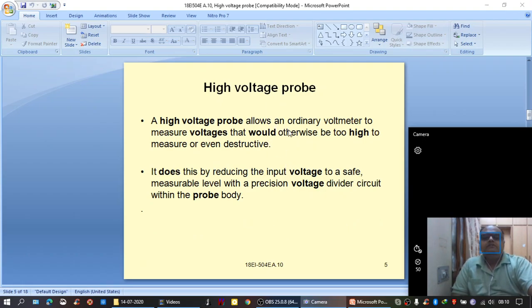A high voltage probe allows an ordinary voltmeter to measure voltages that would otherwise be too high to measure or even destructive. This point you have to observe carefully. A normal DC voltmeter cannot measure the high voltages as such. But when the voltage given to the voltmeter is reduced by tenfold or hundredfold, say for example, if the input voltage to be measured is 4 kilovolts, and if a divide by 100 potentiometer, a decimal divider is used, that means two decimal dividers.